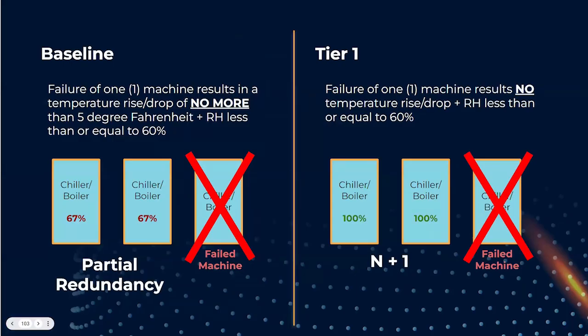So the thinking now is, as a baseline requirement, calculations should be submitted to show that if a single machine is lost, the building does not exceed design temperature set point by more than 5 degrees Fahrenheit and does not exceed 60% RH. This is a performance-based approach versus the more prescriptive requirement from before. There's also an added Tier 1 performance that arranges the equipment in more of a conventional N+1 arrangement, where you have two pieces of equipment, each sized for the peak demand load of the building. So if you were to lose a machine, you do not compromise your temperature and humidity control in the building. Next slide, please.